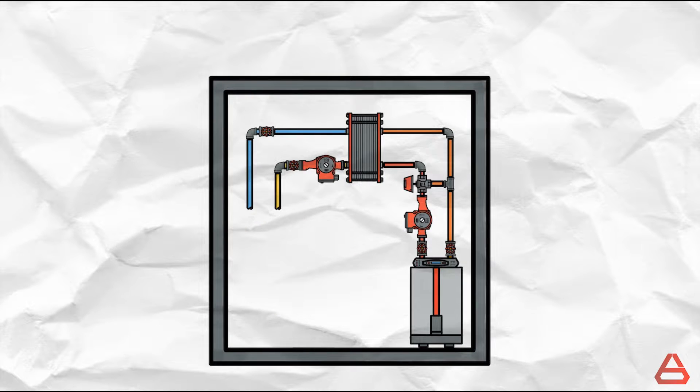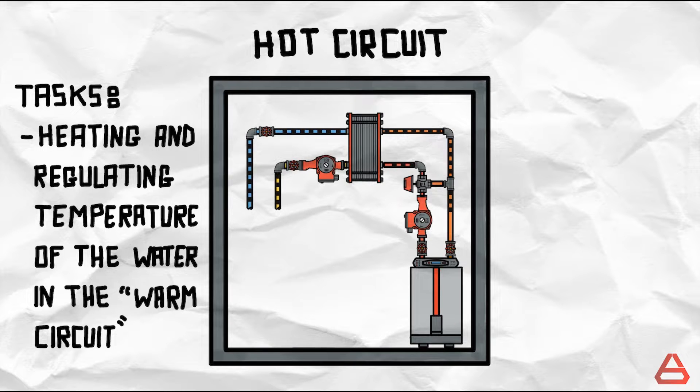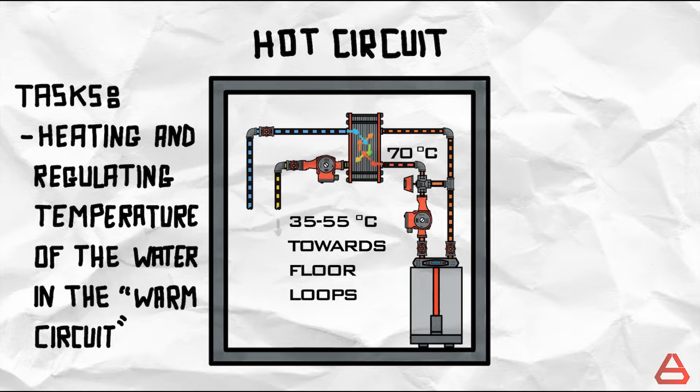The second circuit is a temperature regulating circuit which I refer to as the hot circuit. It is the part of the system responsible for heating and regulating the temperature of the water in the warm circuit. It produces water at high temperatures and exchanges its heat with the warm circuit in a controlled manner to maintain a temperature between 35 and 55 degrees celsius. I'll explain why shortly but for now let's begin with the warm circuit.